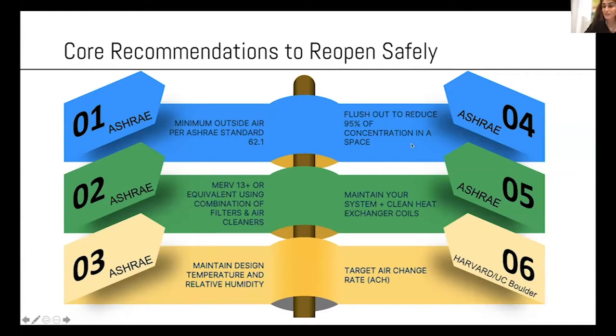Number four, flush out. I have a slide about flush out, and flush out means you clean your space before people come in, either in the morning or at night. Or for example, if you have a community of faith like a mosque and you have two services, you wait and you clean the air between the two services. Same thing if you have a classroom or theater, etc. Number five is to maintain your system, which goes without saying. You can design the best building, but if you don't maintain it, you're not doing a good job.